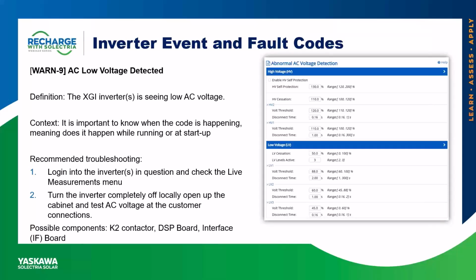As for recommended troubleshooting, you would want to start by turning the inverter completely off, opening it up, and testing for AC voltage at the customer connections. If right away you are seeing a strange value on your meter, this issue may be external from the unit. If the values are close to what the inverter wants to see, you can turn the inverter on and proceed to the second recommended troubleshooting step, that being to log into the inverter and check the live measurements menu.